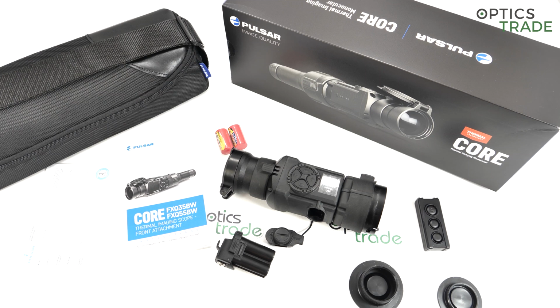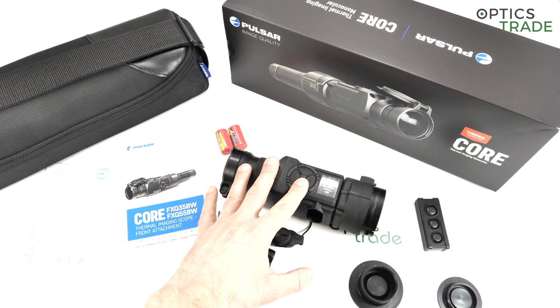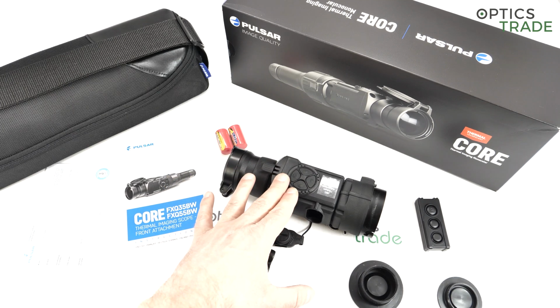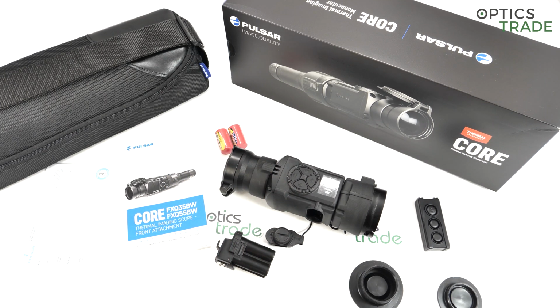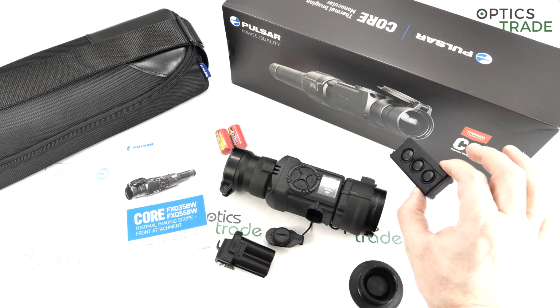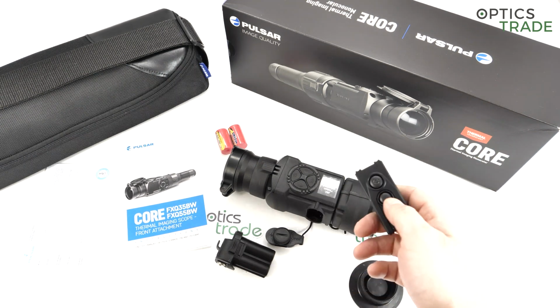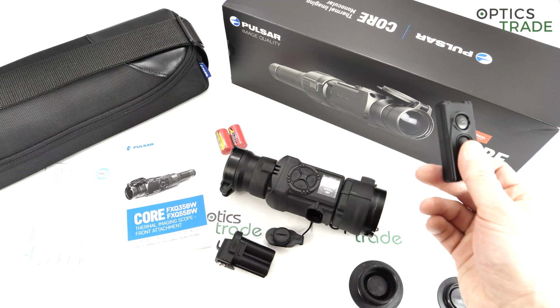This happens if no calibration is made for about 2 or 3 minutes, then you see that the image quality is fading. With these devices, it's really important that you're able to do the calibration manually, because when you're using them as a clip-on, if the calibration is automatic, then you always have to check in the lower part of the screen when the calibration will happen, because it counts the seconds until the calibration, so that you are really ready not to take the shot at the time when the image freezes. And this is a great addition, because you have a remote with your device, so you're able to calibrate the device via remote.